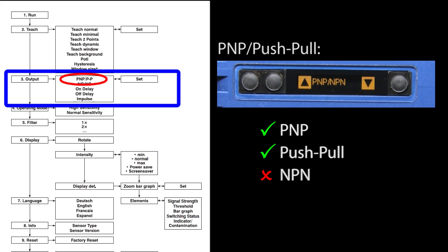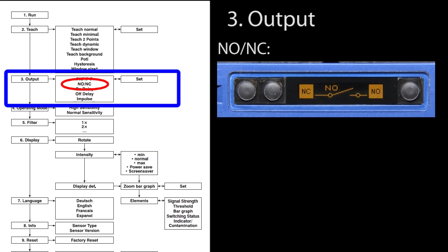You can select the output type to be PNP or push and pull. The title of this submenu is PNP NPN and there is a menu selection for MPN but you can't actually select it on this sensor because the extra pin you would need to add the NPN output is used for a teach input. This is just a generic menu that is used on multiple sensors. You can select normally open or normally closed. Some folks call that light on or dark on.